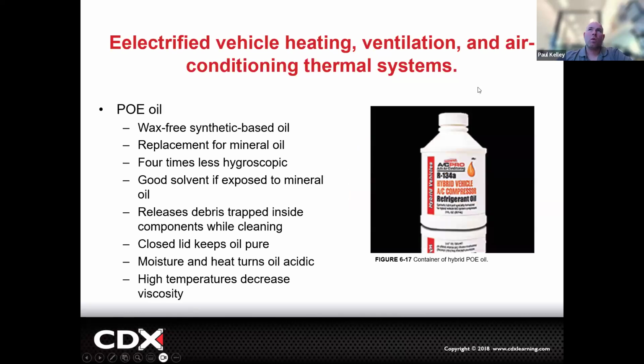When we go to work on this system, a lot of times it's going to call for some sort of POE or ND11, specifically ND11 is a type of POE, but it's going to call for a specific oil. You're going to look on the sticker, it'll call the oil out and that's the oil you're going to use. For example, wax free, replacement for mineral oil, four times less hygroscopic, good solvent if exposed to mineral oil, releases debris trapped inside components. Keep the lid closed, because if you have the lid off, that's going to absorb moisture and it's going to be ruined. Moisture and heat can make it acidic, right?